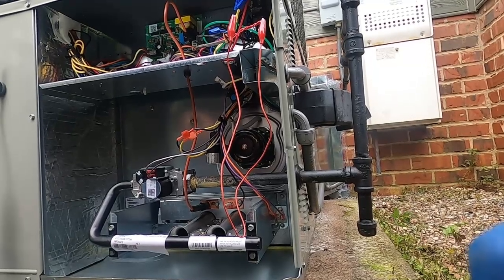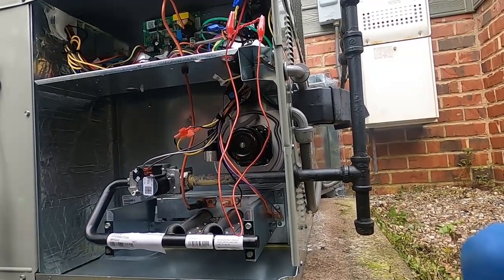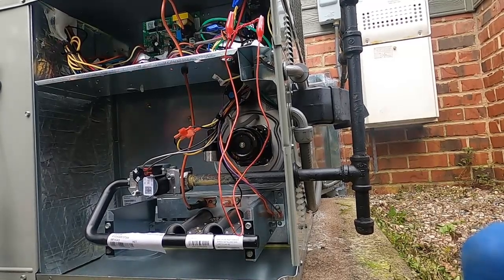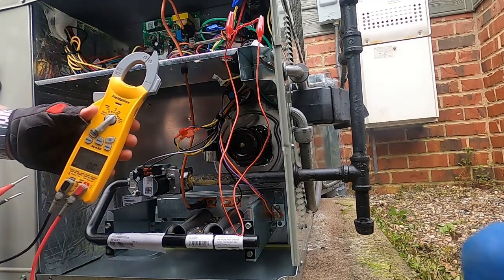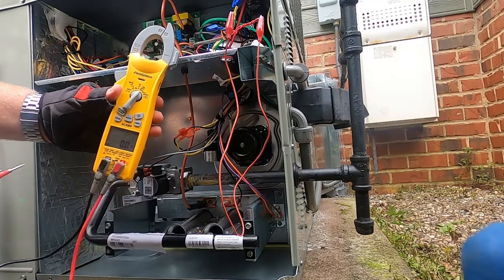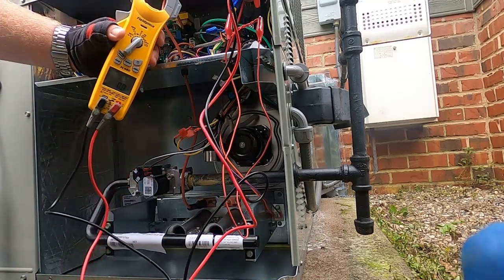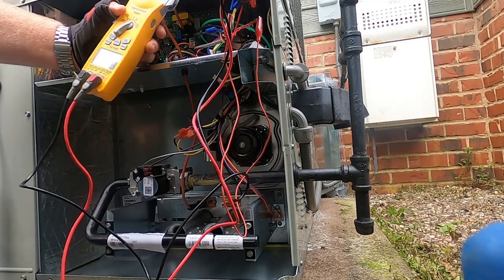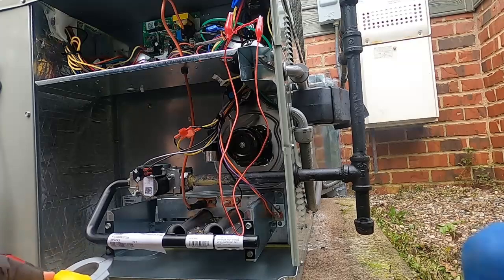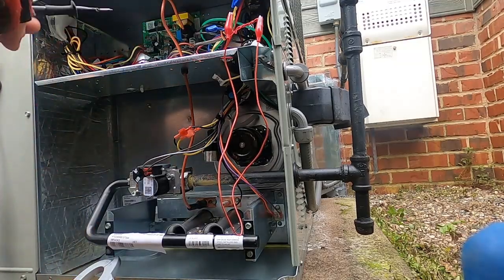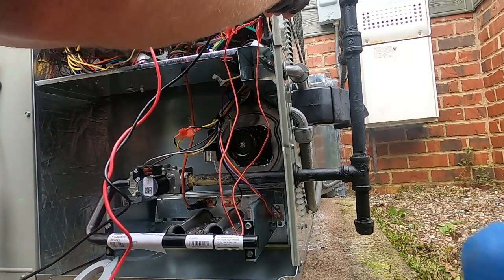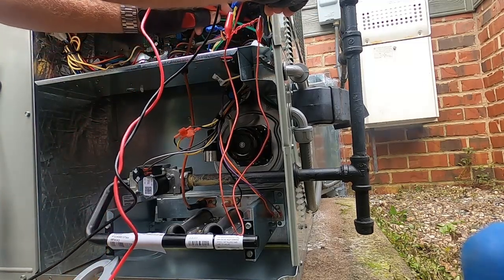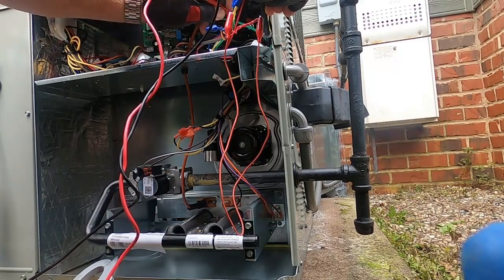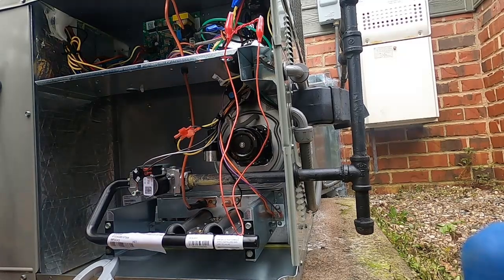While I'm here, I also have to get that paperwork. Incoming voltage, and no, I'm not using the Testman. So 246, and then there's a place they want you to check each leg to ground, which is fine. 123, 122. So we're good on our voltage.